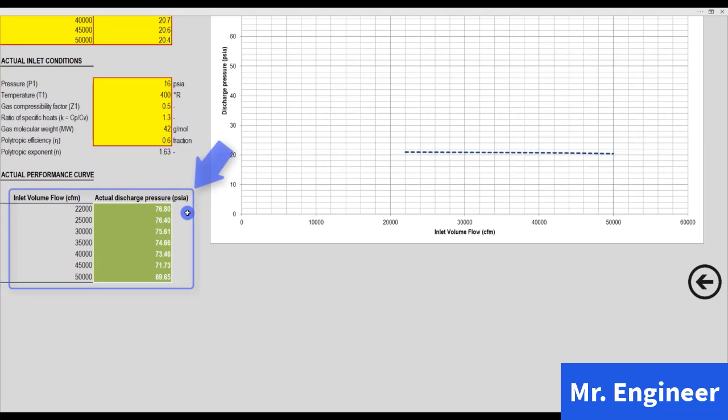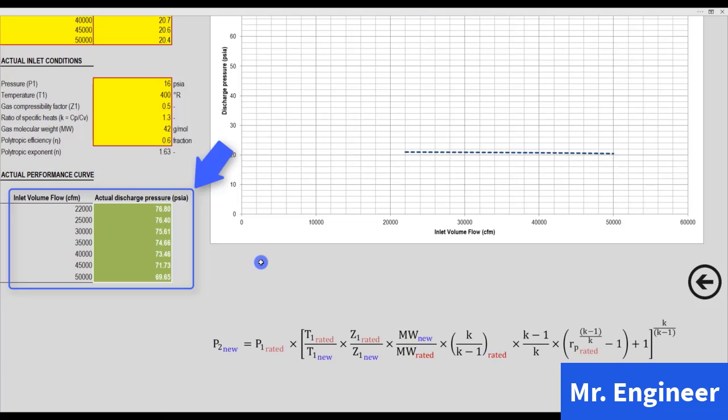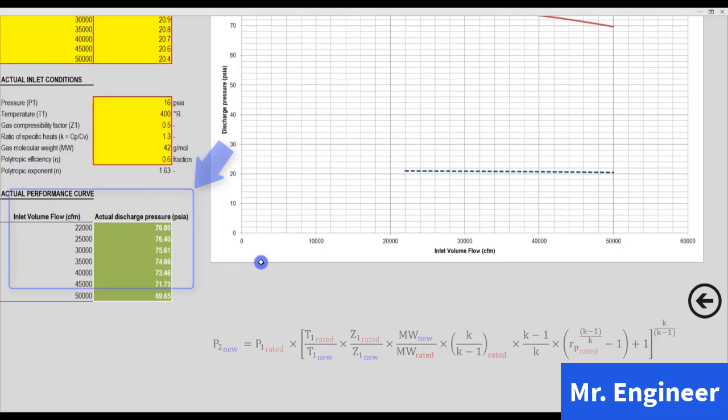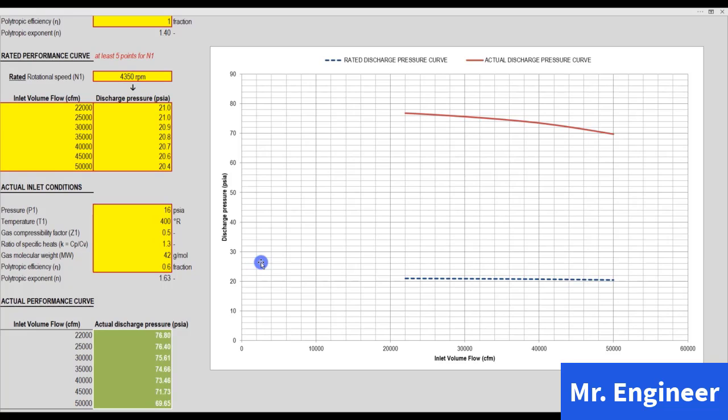Now, here, based on these new inlet conditions and for each volume flow, I have calculated the actual discharge pressure using the following equation. Recall, this equation was discussed in detail in a previous video. Notice here that under these new inlet conditions, the discharge pressure has increased compared to the rated performance. For example, for an inlet volume flow of 30,000 cubic feet per minute, at rated inlet conditions, the compressor is expected to develop a discharge pressure of 20.9 psi.